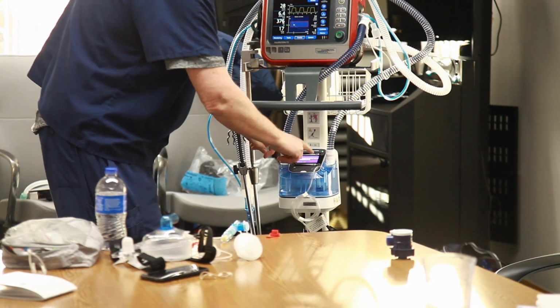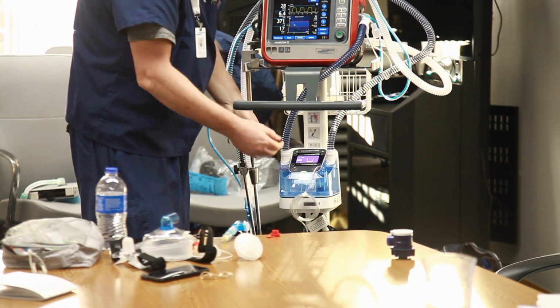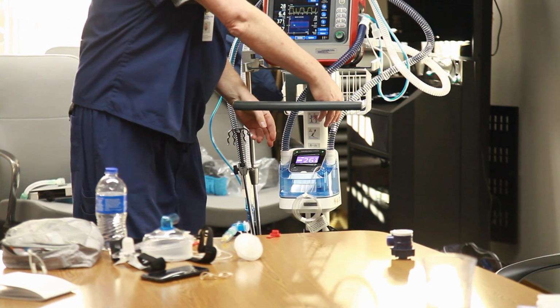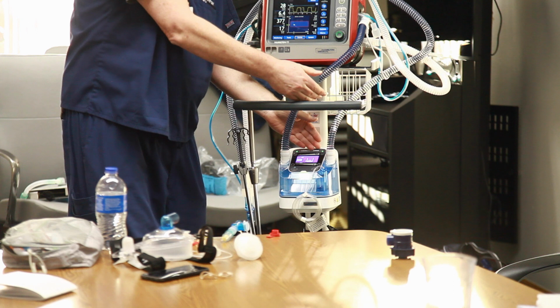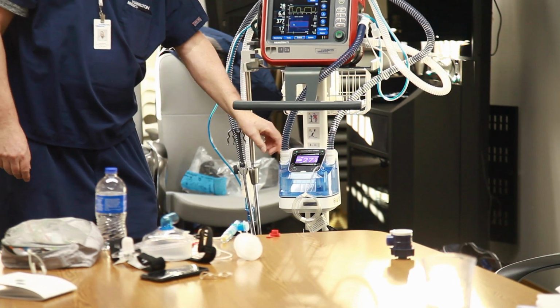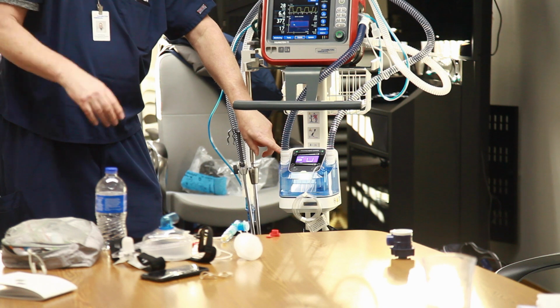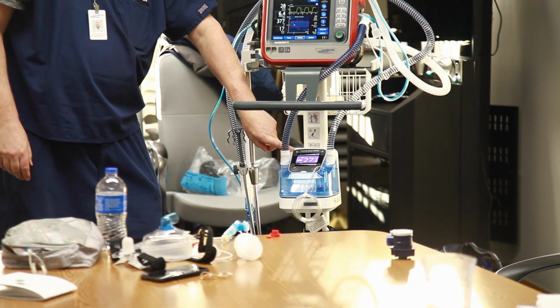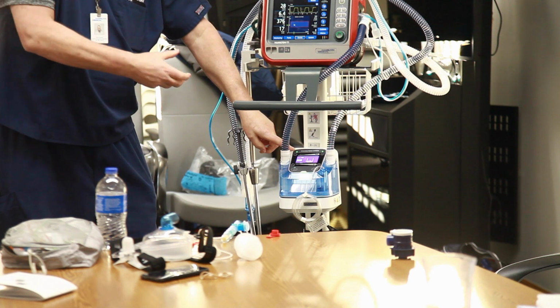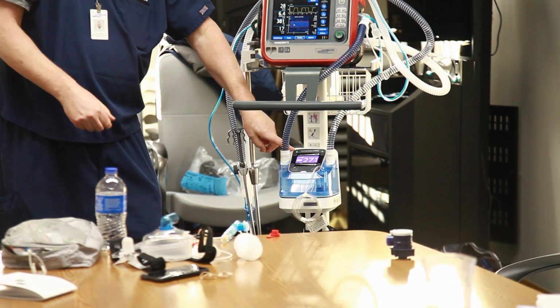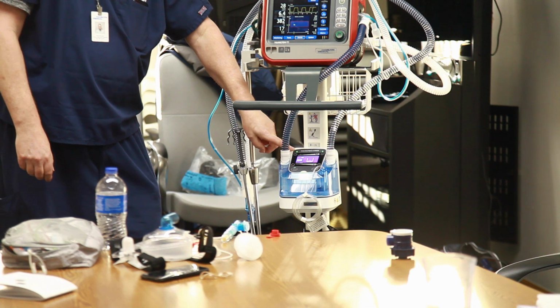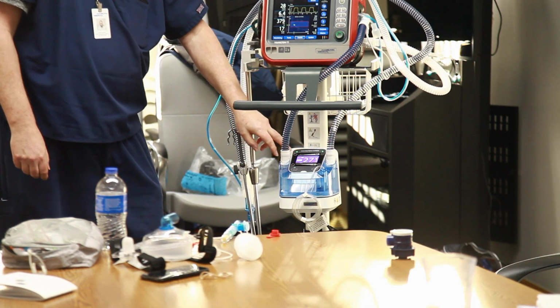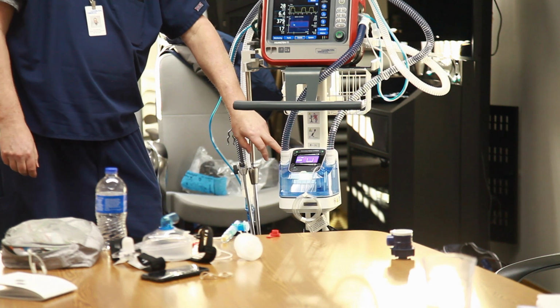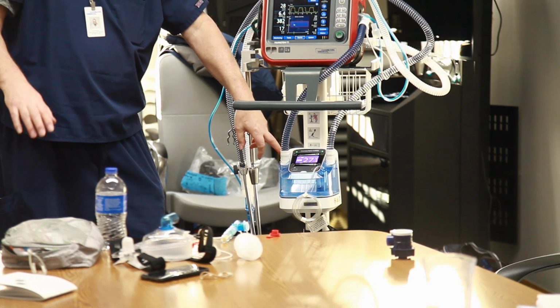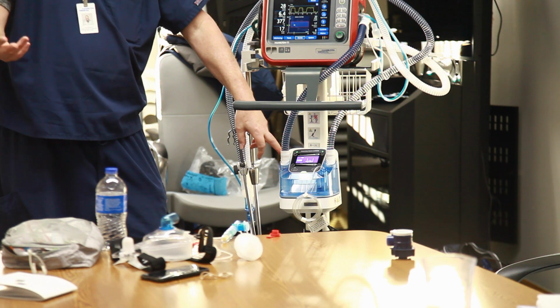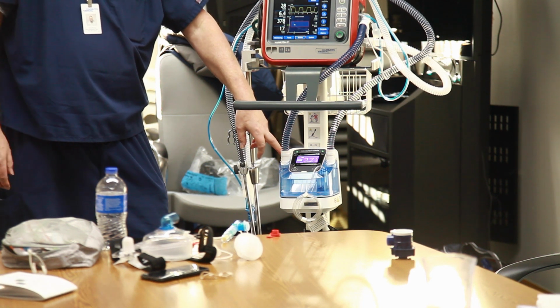You see I have 2 little green things here. I could actually change these if I wanted to gain a few inches and swap these from side to side. Just realize these have to be lined up. If one of these isn't lined up into that plug right, it'll be red. So I might be red here and green here. Just take it out, wiggle it around, push it back in until it gets to be green. If it doesn't, then swap these back and see if that red one follows, or if it stays here, then the humidifier's got an issue. But that's way more troubleshooting than you need to know. Just call me if you have issues with that, and we'll walk through it.